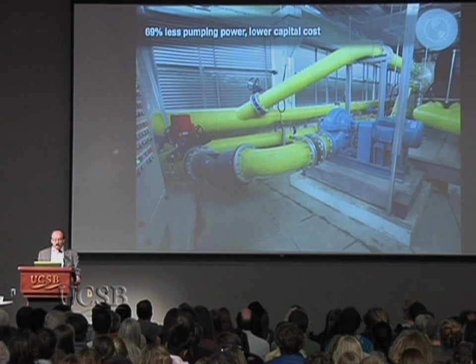But first, we should stop wasting most of the energy used by the pumps, fans, and other motor-driven equipment. For example, pumps, the biggest use of motors, move liquid through pipes. A Dutch engineer we were working with redesigned a typical industrial pumping loop to use an order of magnitude less energy and cost less to build. I think he had at least an 86% saving, maybe 92, just by using fat, short, straight pipes instead of skinny, long, crooked pipes. We all learned this stuff from a master engineer in Singapore, and this is one of his latest installations, which saved 69% of the usual pumping energy at reduced construction costs, partly because the pumps, motors, and electricals are all much smaller.